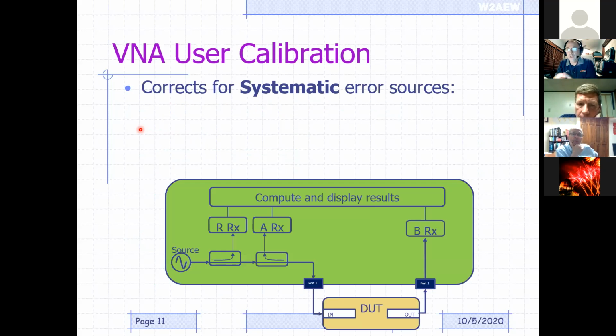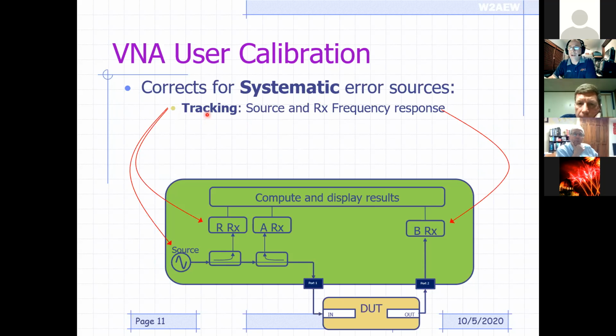So a little bit deeper. The user calibration corrects for what we can call systematic error sources. Systematic error sources are things like what we call tracking errors. And this is measuring and calibrating out the source and receiver frequency response. So we want to flatten those out, take them out so they're not part of our measurement. That's part of what the calibration does.